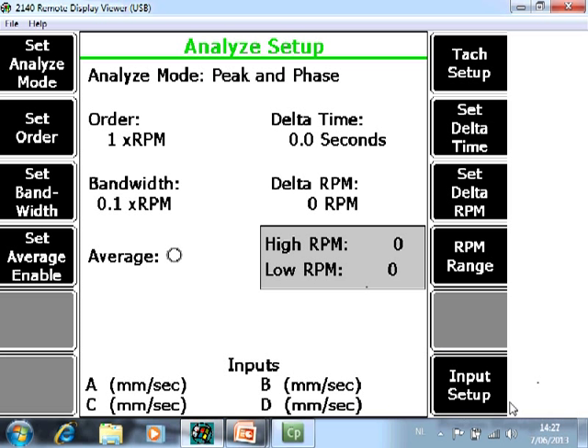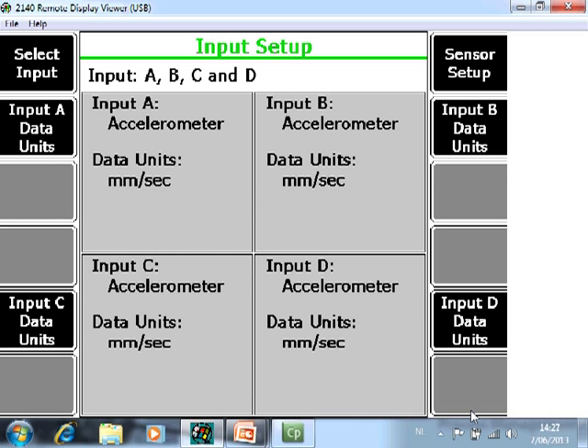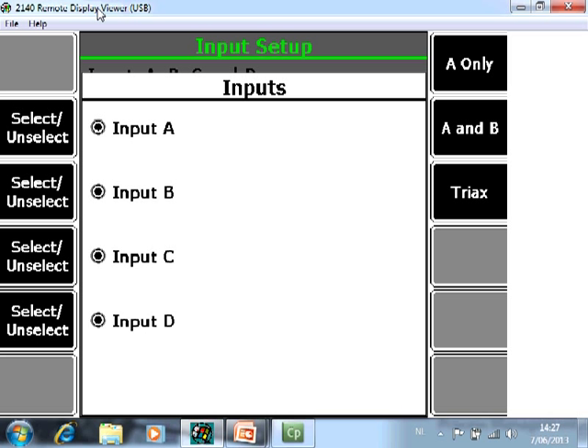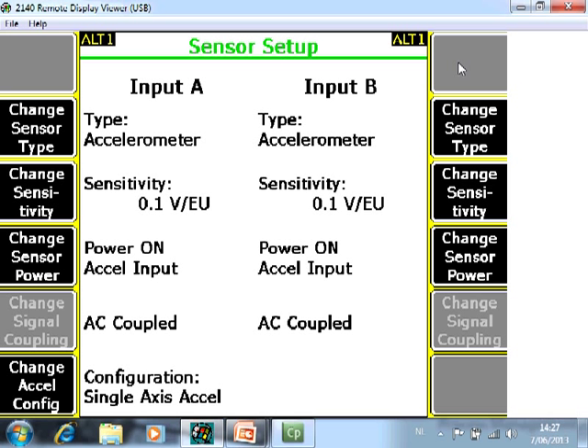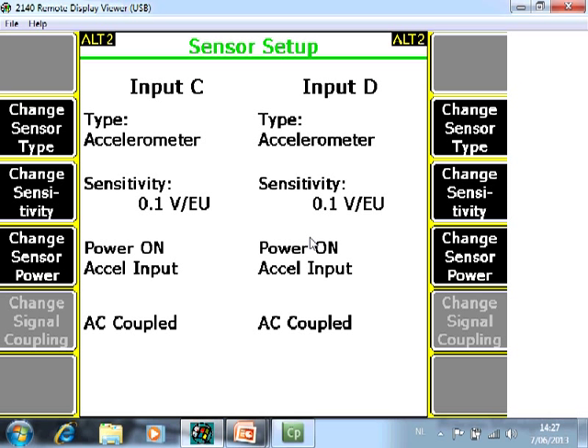Input Setup F12. Here you specify the kind of sensors that you want to use. First of all select input F1. Here you specify how many channels you want to measure simultaneously. In this example we will measure 4 channels simultaneously. F7 sensor setup. Here you specify what kind of sensors you are using. In this example we are using accelerometers with the standard sensitivity of 100 millivolt per engineering unit and power on. Sensor B is identical, C and D as well.